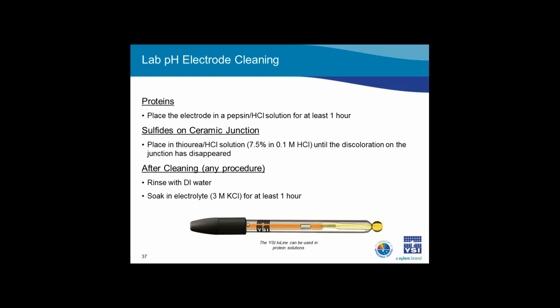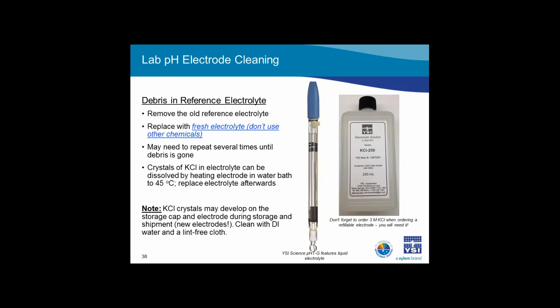After performing any of the discussed cleaning procedures, thoroughly rinse the electrode with DI water, then soak it in 3 molar KCl for at least 1 hour before attempting a calibration. Soaking in 3 molar KCl, potassium chloride, can also help rejuvenate a reference junction that has accidentally dried out. Because I know no one's going to let it dry out on purpose, right?